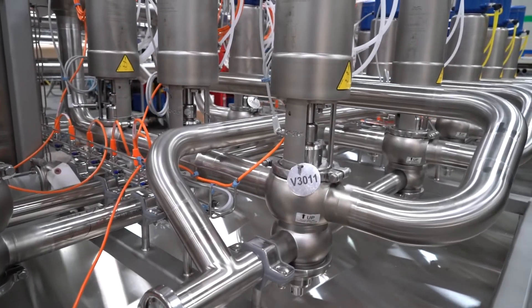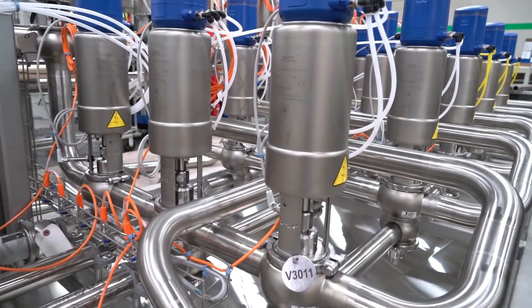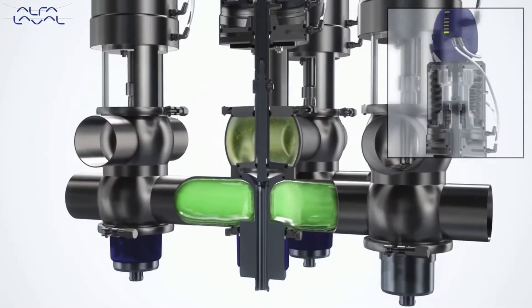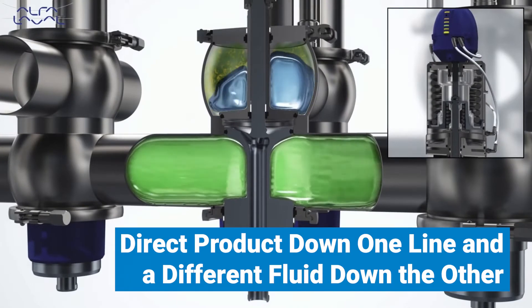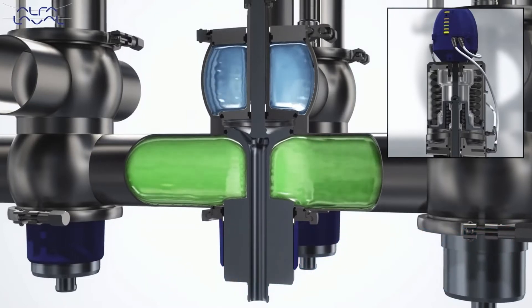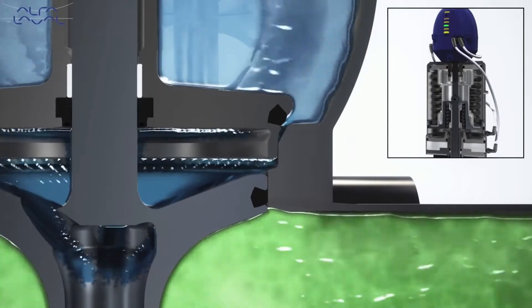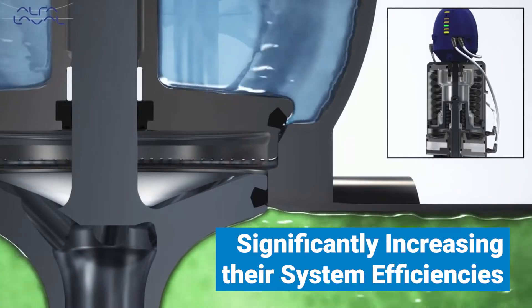These manifolds use Alfa Laval Mixproof, single seat, and reverse acting single seat valves. Mixproof valves have two sealed chambers that allow processors to direct product down one line and a different fluid down the other without the risk of cross-contamination. This feature enables the sauce processor to run multiple sauce products simultaneously, or even CIP solutions down one line while running sauce down the other, significantly increasing their system efficiencies.